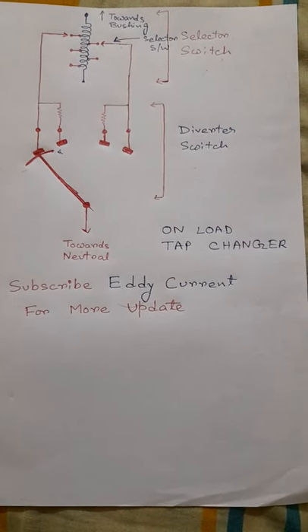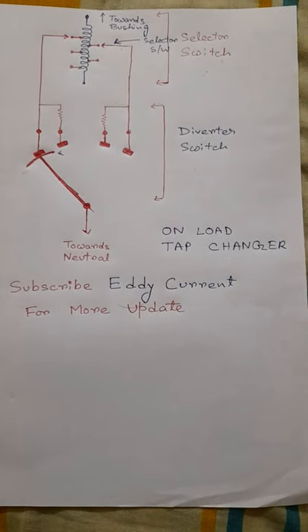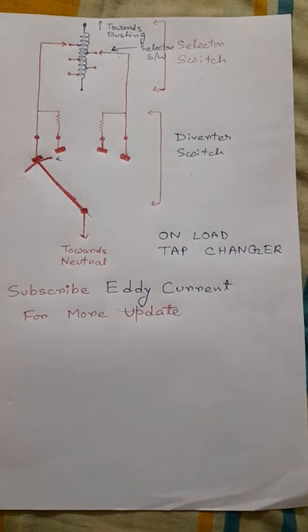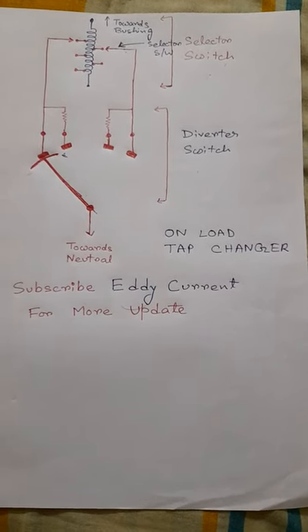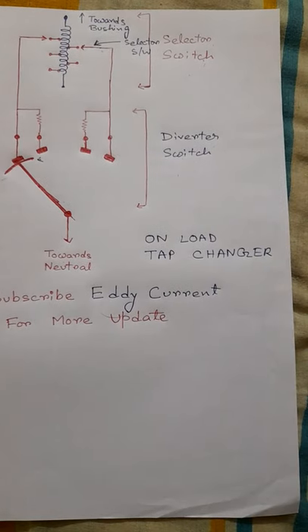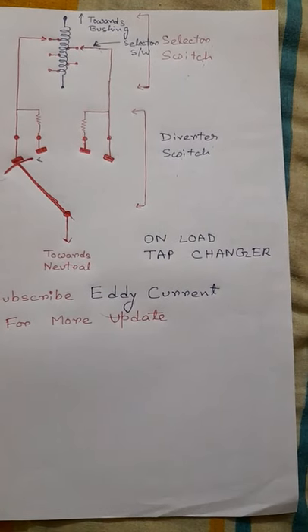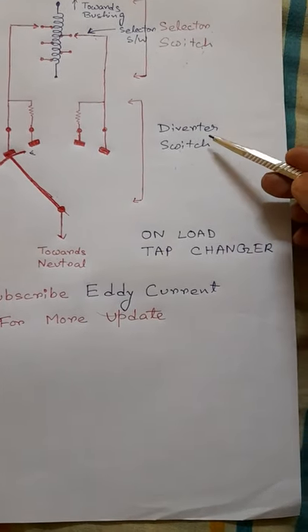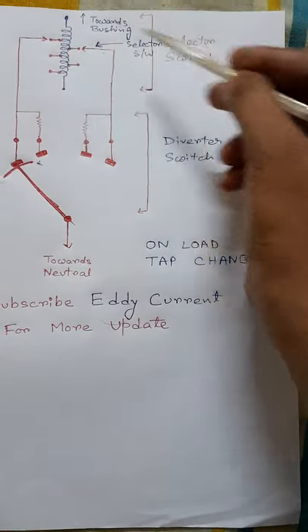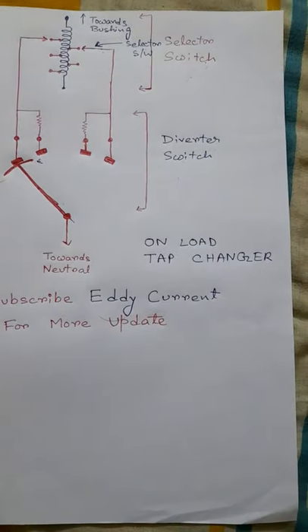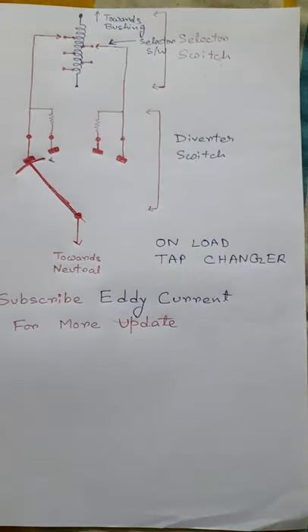Hello friends, welcome back to Eddy Current channel. In this video, we will discuss the operating principle of an onload tap changer or OLTC using this drawing. In an onload tap changer, tap changing operation is performed by two types of switches: selector switch and diverter switch. Actual tap changing is performed by selector switch, whereas diverter switch is used to divert the load current during tap changing operation.